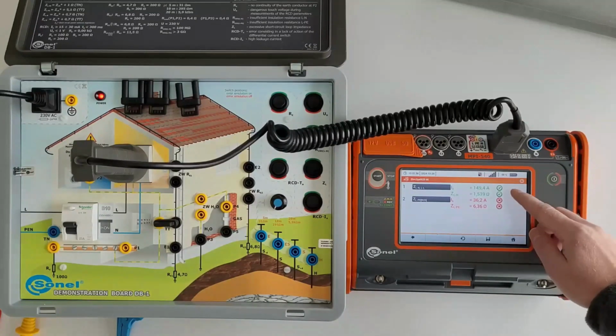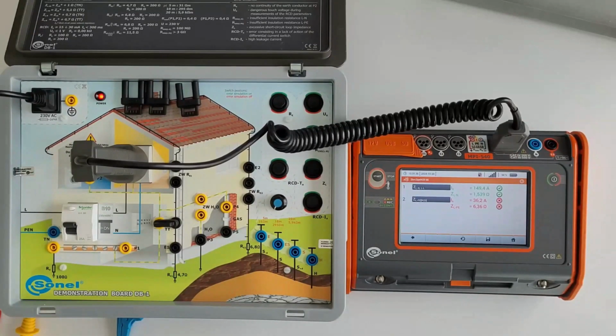This is the first information. If we measure the loop impedance and the live-neutral and live-protective values are very different, it is the first point by which we check whether we have a TN or TT system.